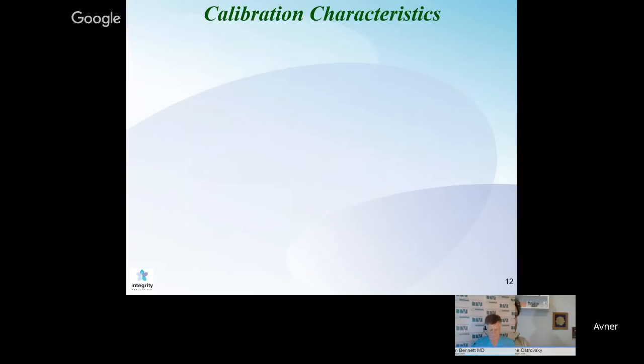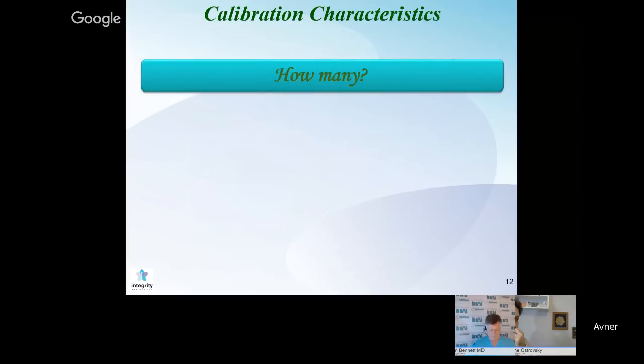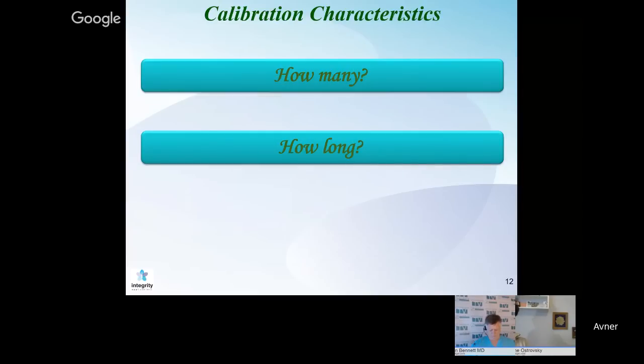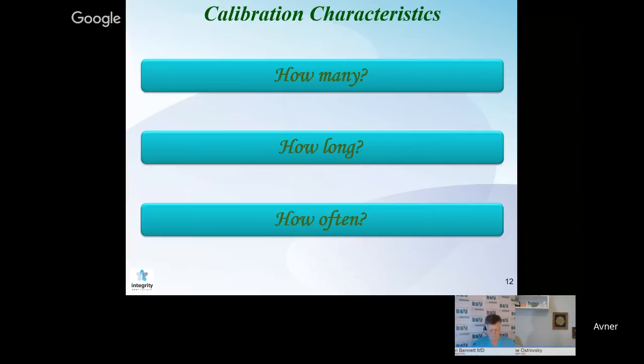I mentioned at the beginning that whenever you're talking about a non-invasive device, it must be calibrated. That's the way to teach the device about the correlation between the signals and the glucose readings. And when you're talking about calibration of a non-invasive device, there are immediately 3 questions that must be asked. How many prickings are involved in the calibration process? We mentioned one of the examples previously that requires at least 200 prickings. How long does it take? Examples that I mentioned previously required everyday calibration that requires 3.5 hours and 8 prickings. So you can imagine that this is not exactly considered non-invasive. And the last question is, what's the validity of the calibration, or how often do you have to repeat it?